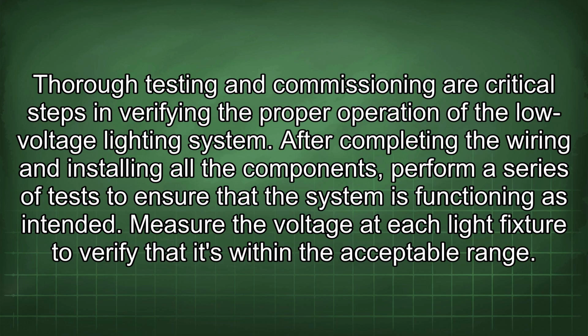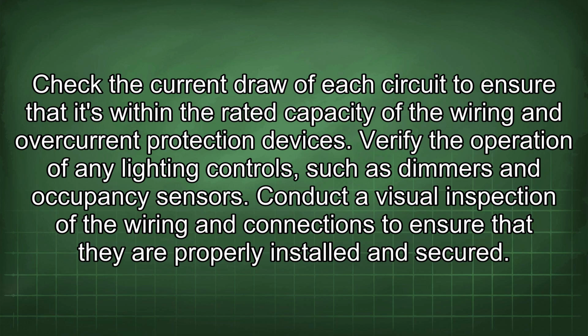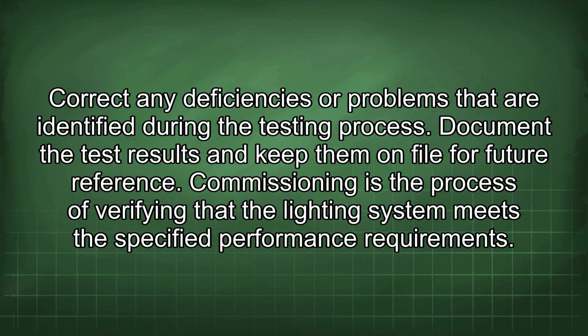Thorough testing and commissioning are critical steps in verifying the proper operation of the low-voltage lighting system. After completing the wiring and installing all the components, perform a series of tests to ensure that the system is functioning as intended. Measure the voltage at each light fixture to verify that it's within the acceptable range. Check the current draw of each circuit to ensure that it's within the rated capacity of the wiring and overcurrent protection devices. Verify the operation of any lighting controls, such as dimmers and occupancy sensors. Conduct a visual inspection of the wiring and connections to ensure that they are properly installed and secured. Correct any deficiencies or problems that are identified during the testing process. Document the test results and keep them on file for future reference.